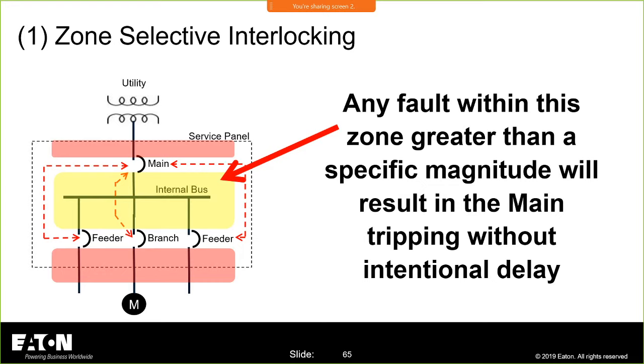When they originally talked about fuses, they were going to say that the arcing current had to be in the current limiting region of the fuse. And I think Vince Saporito was sitting at the table and said, hold on. We have a requirement on breakers for zone selective interlocking that will give you a 0.07 seconds clearing time, but yet you're going to tell the fuse it has to act faster than some of the slower technologies that are in 240.87.